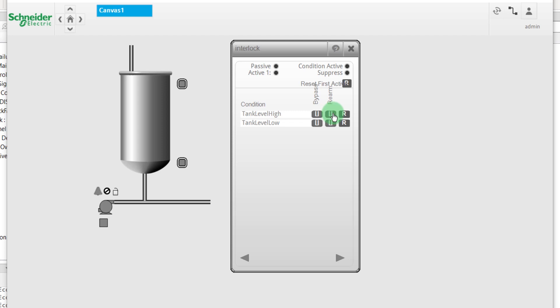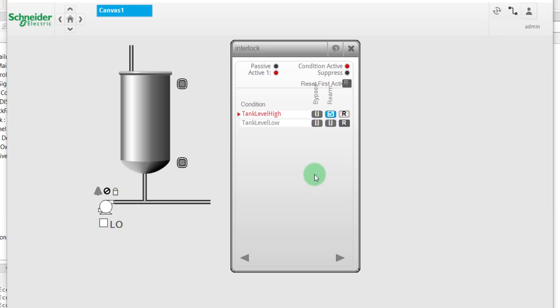If your interlock needs to be rearmed manually, you have to check the rearm box. In this way, the reset button will blink and you will have to click on it to rearm your interlock. Finally, the red triangle indicates the first condition that has been activated. You can reset it with this button.